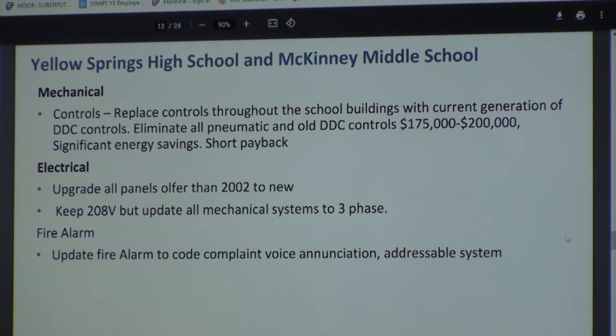They're not compatible with switching over to electric. If you bought all new air handlers and they're all 208, then you've committed yourself to 208. You could buy transformers that would convert 480 to 208, but then you've got a bunch of transformers. It's possible, but I see that as the complexity.